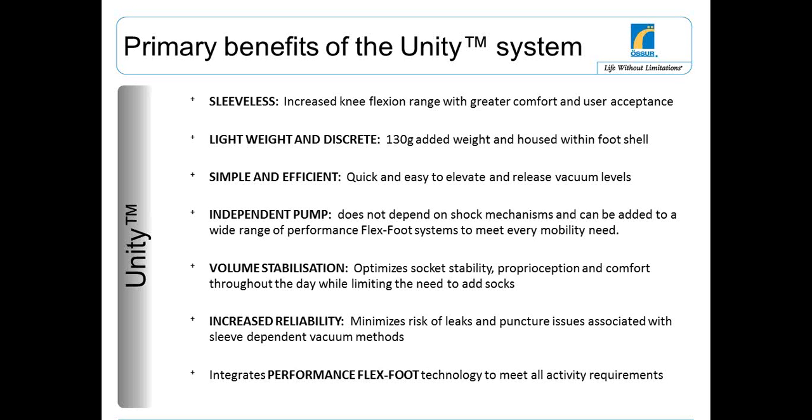It's a simple and efficient pumping mechanism that you'll see. It's quick and easy to elevate the vacuum, and also because of the tri-function valve we have, it's very easy for folks to release the vacuum levels as they need to either take the prosthesis off or potentially to decrease the vacuum levels, for example, if they're sitting for a long period of time.